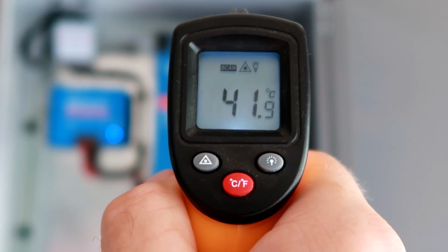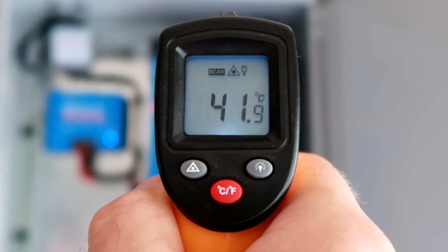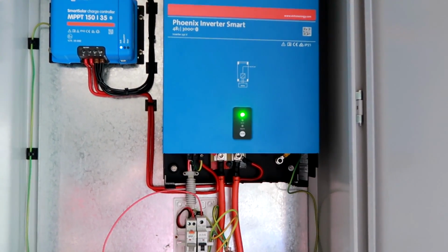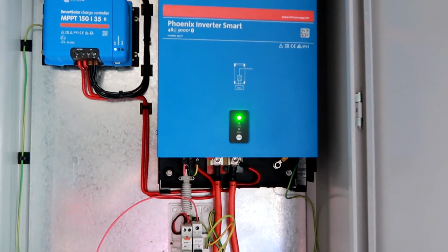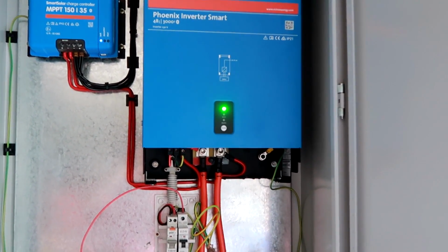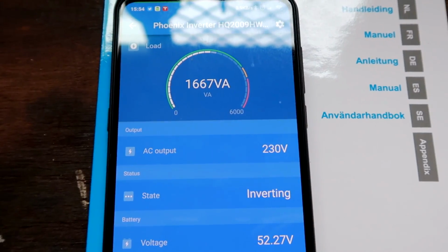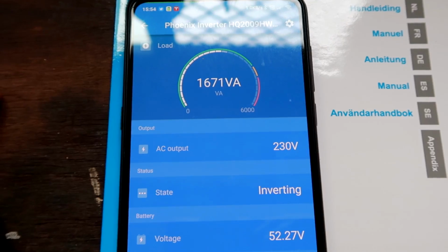Got now 41 degrees on the outside of the inverter, but the alarm has cleared and there's no over temperature warning anymore on the app as well. So I guess it has something like 45 degrees internal temperature shut off, and that triggers the alarm. We are still charging with 1700 watts, so that seems to be the sweet spot for this outside temperature, and we don't get any over temperature warnings anymore at the moment.